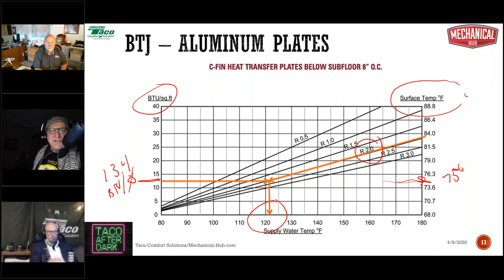So under design conditions, in order to get a 75 degree floor surface temperature with a carpet and pad with an R value of 2.0, to get 13.4 BTUs per square foot, I need about 122 degree water. Does that make sense to everybody? That's pretty simple. That's how you work this chart. Now, I have another question for you. Here's another pop quiz. Isn't this fun? It's pop quiz day. 13.4 BTUs per square foot, that's when it's 0 degrees outside, right?